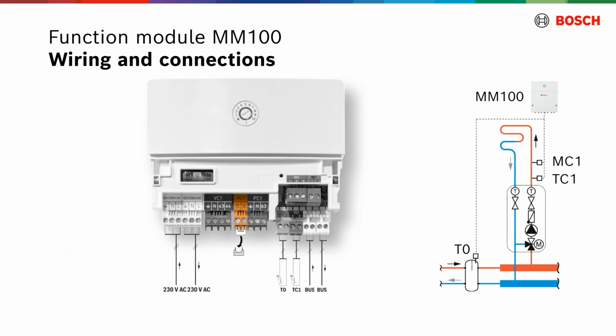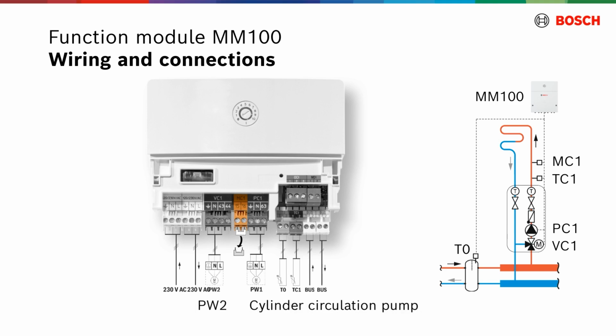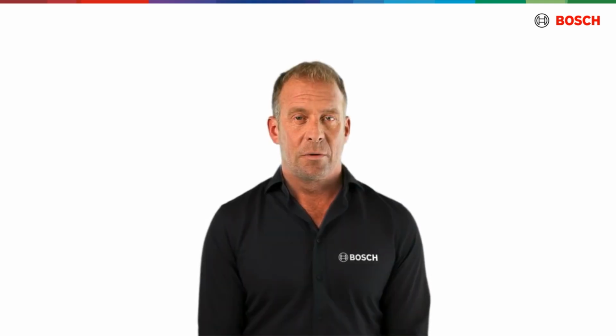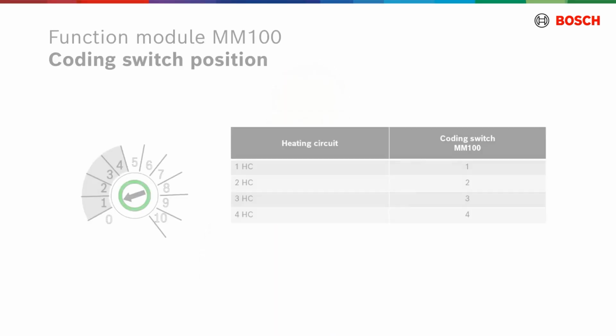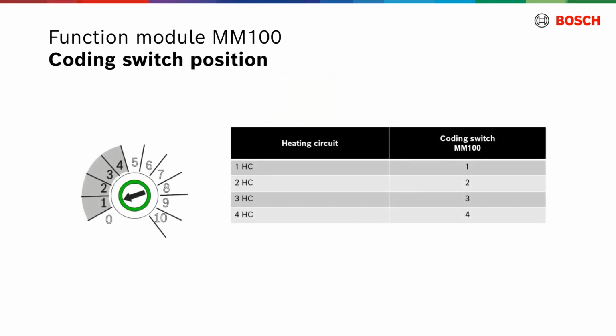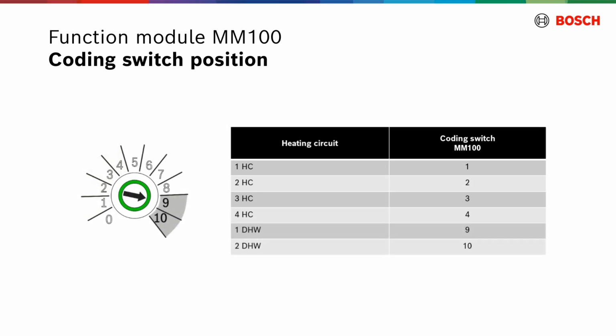Function module MM100 activates heating circuit pump PC1 and the mixing valve motor VC1 of the assigned heating circuit, or cylinder primary pump PW1 and circulation pump PW2 in the cylinder circuit. To ensure the proper functioning of the connected heating circuit, the valid position of the coding switch should be chosen. Heating circuits assigned to the module should be addressed from 1 to 4. If the module serves the cylinder charging circuits, the coding switch has a position from 9 to 10.